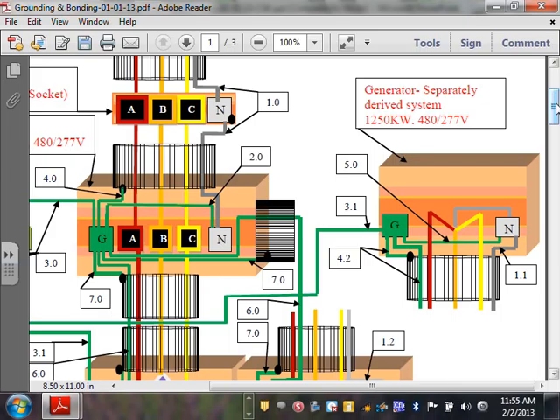The same thing, a wire size, and also, guys, the conduit coming to the generator has to be bonded. Same thing, supply side bonding jumper. If you put a circuit breaker like we said here, that will make this one an equipment grounding conductor, and also this piece will be treated as an equipment bonding jumper, load side. So these two will be the same size. If the circuit breaker is here, they're equipment grounding conductors. If the circuit breaker is here, that will be a supply side bonding jumper.